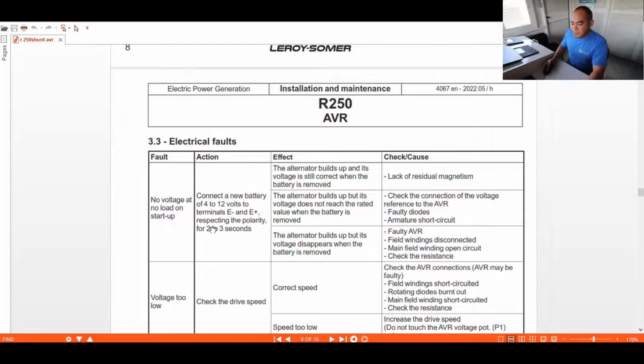Okay, the effect is that the alternator builds up the voltage. It is still correct when the battery is removed. The alternator builds up, but its voltage does not reach the rated value when the battery is removed. Then you have to check the connections of the voltage reference at the AVR, faulty diodes, and armature short circuit. So this is what you are going to check.